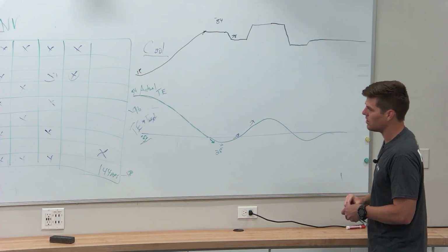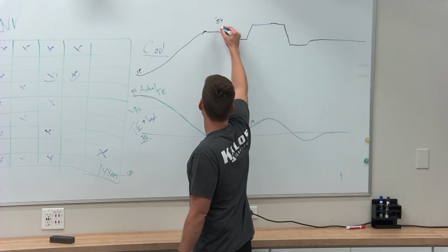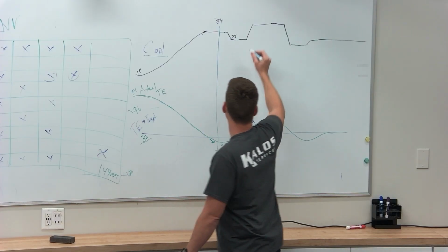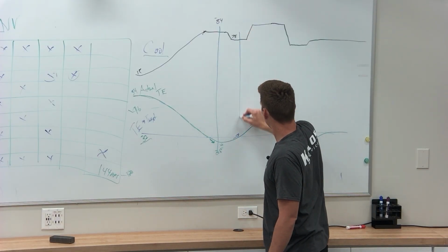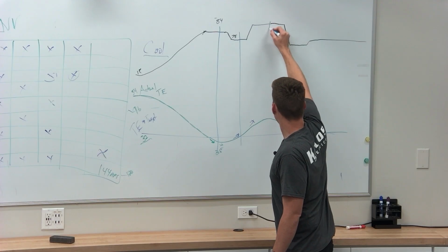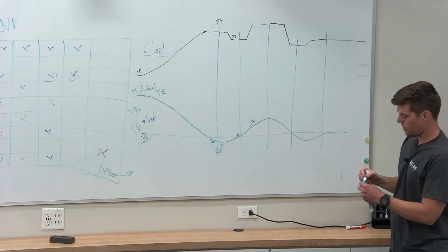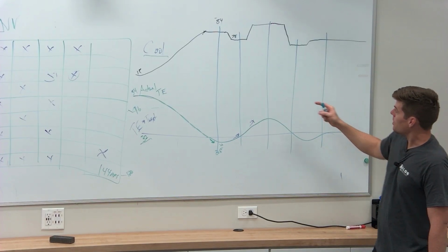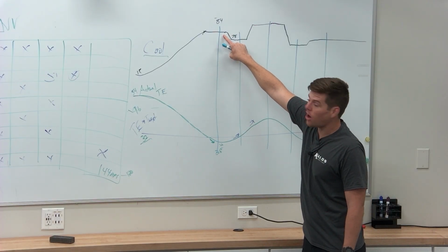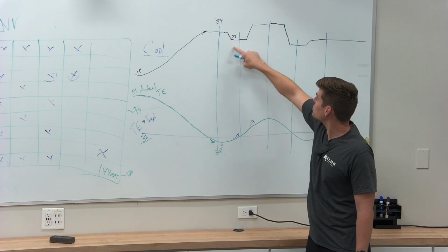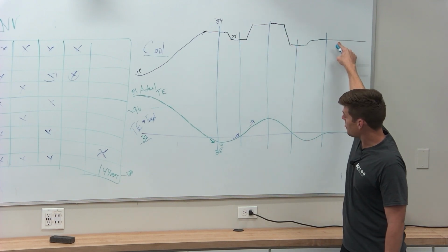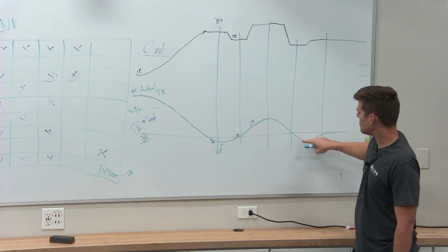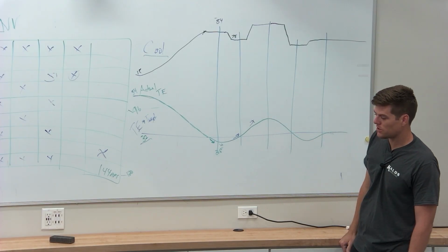I wish I had one more color. Because again, Service Checker is looking at this, right? It's looking at the correlation between these things. They're connected over time, right? We can see the cause and effect here. We see the compressor speed changes, right? And how they affect the saturation temperature of our refrigerant on our suction line.